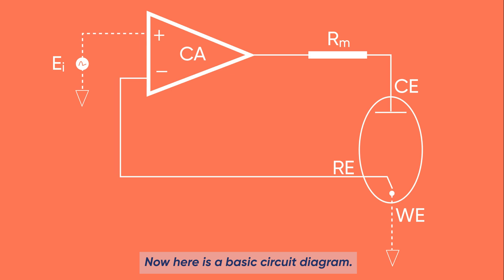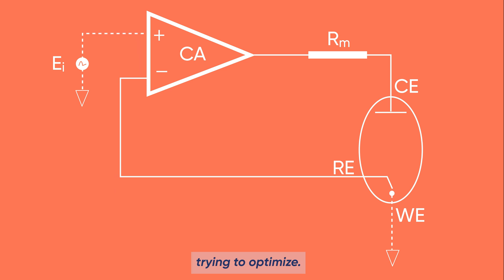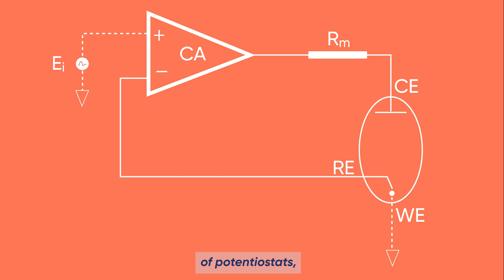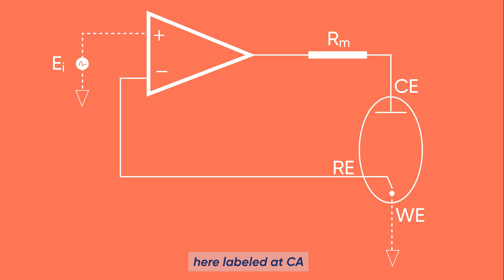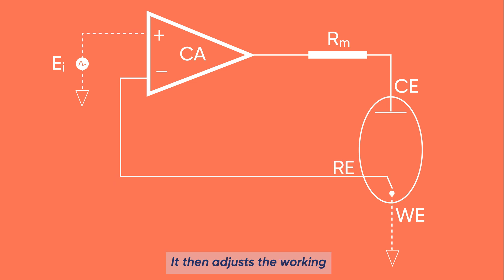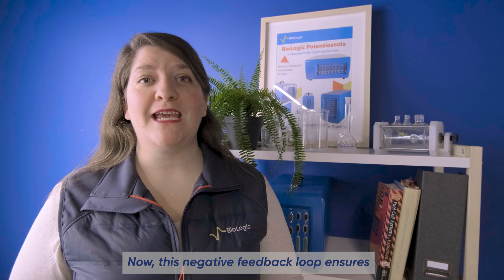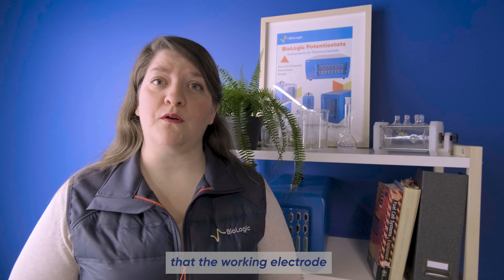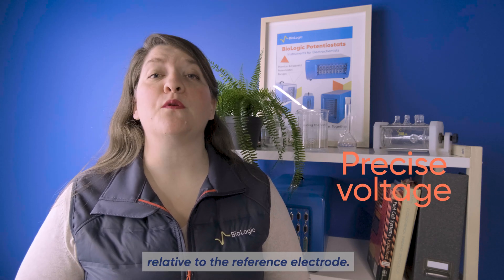Here is a basic circuit diagram. Keep in mind that this setup can vary depending on what you're trying to optimize, and that's why at Biologic we offer two different ranges of potentiostats to cover different needs. A potentiostat circuit uses a control amplifier — here labeled CA — to compare the working electrode's voltage with that of the reference electrode. It then adjusts the working electrode's potential via negative feedback until the voltage matches, ensuring that the working electrode maintains a precise voltage relative to the reference electrode.